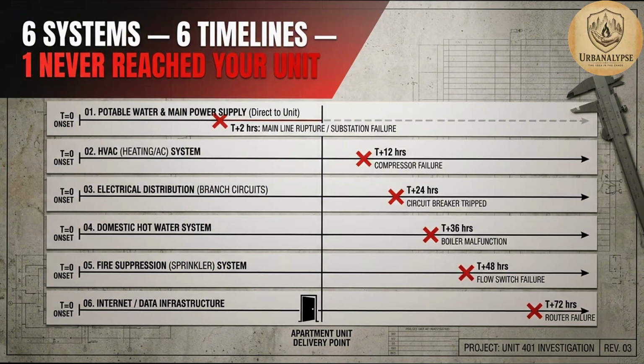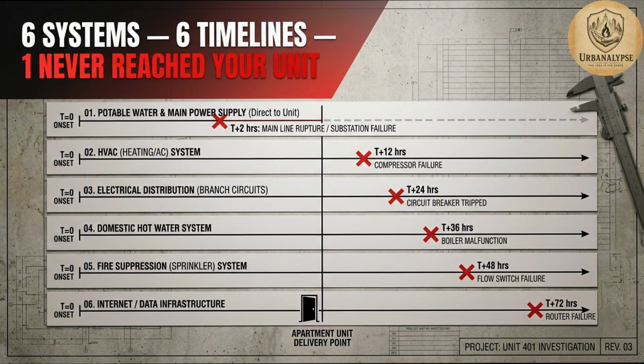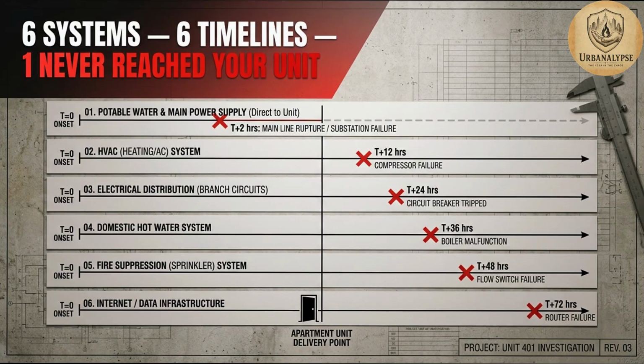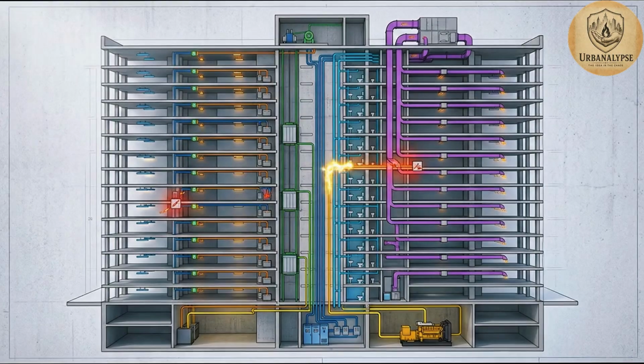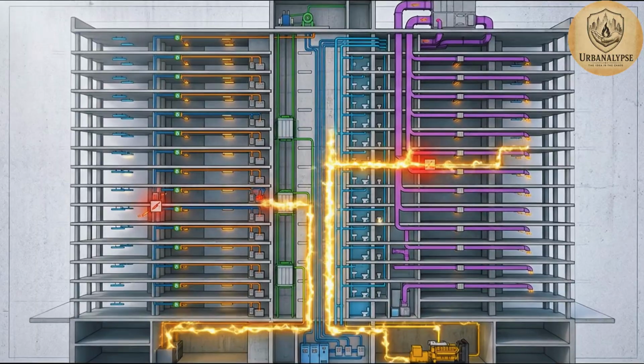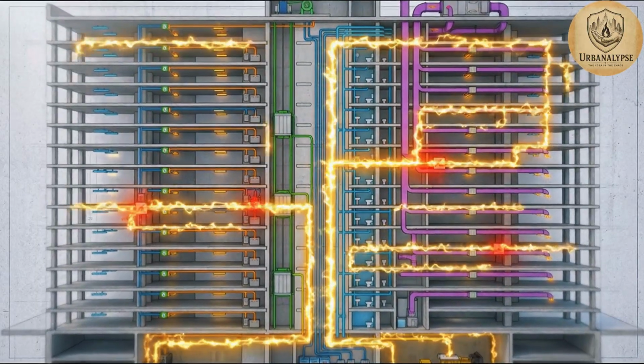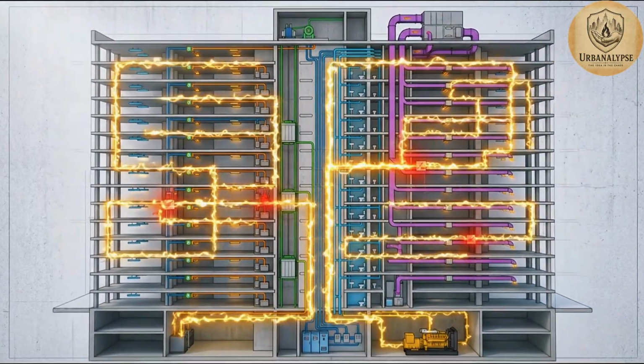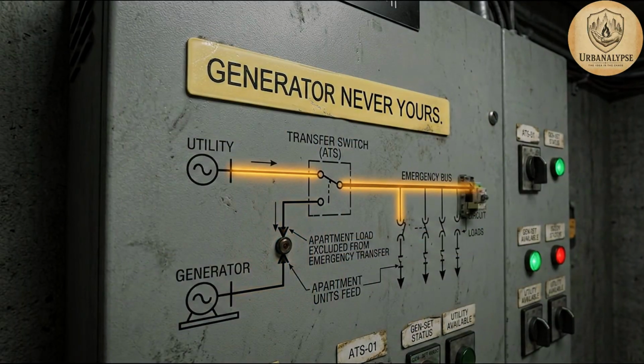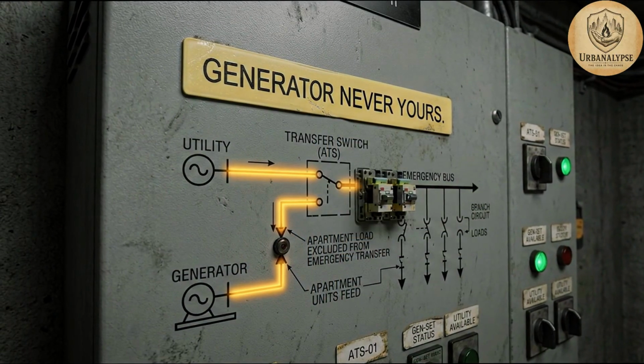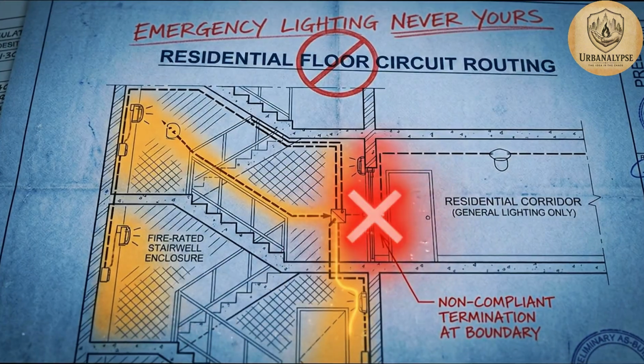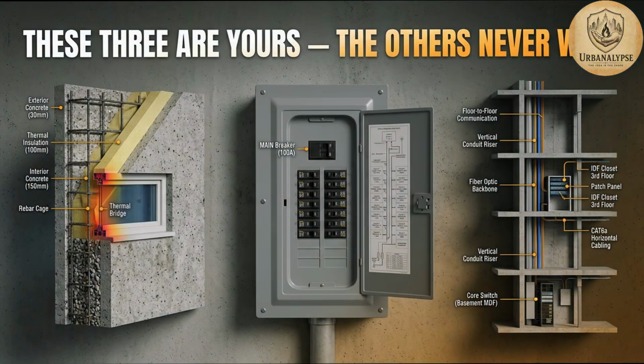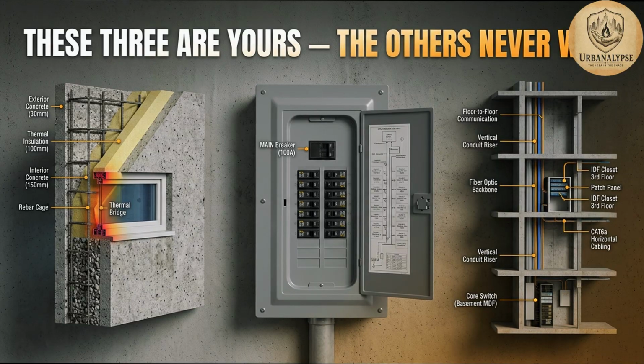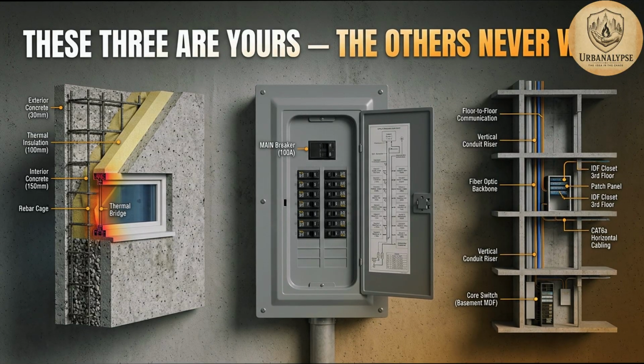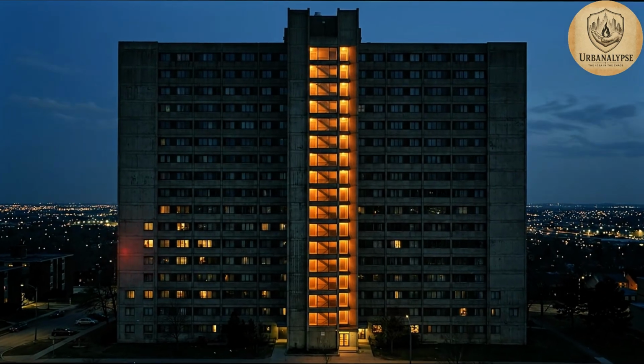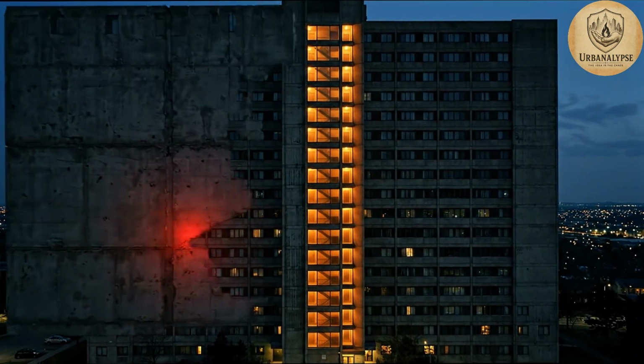A 20-floor building losing grid power is never a single event. It is 6 overlapping systems, failing across 6 different timelines, each governed by its own physics, and only one of those 6 systems was ever engineered to reach your apartment directly. The generator was never yours. The elevator recall was never yours. The emergency lighting was never yours. What is yours is the 4 to 6 hour thermal window, the sub-panel map you built in advance, and the floor-by-floor data network you helped create in the first 20 minutes.